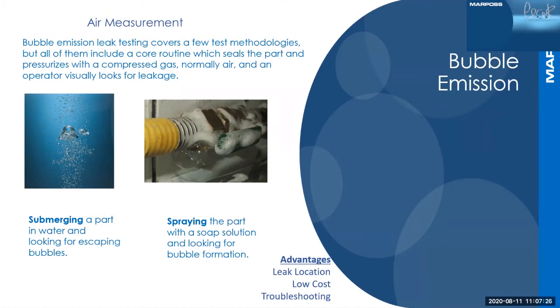Spraying, more commonly known as soap solution, is nothing more than pressurizing a part and spraying the joints or suspected leak location with a soap solution. If gas is escaping, it will form bubbles. If you have ever installed a natural gas line for a dryer or stove, you more than likely used this reliable method to make sure that natural gas was not leaking.